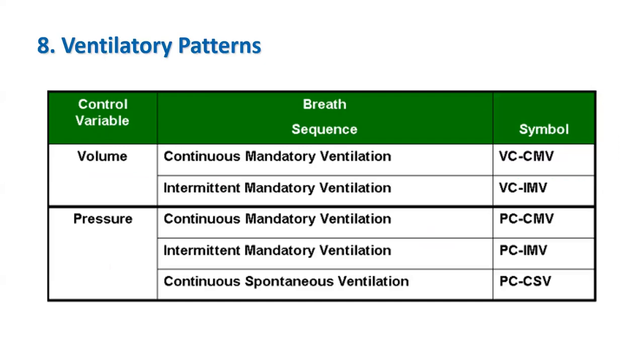Maxim 8 is simple but fundamental. It says that if you combine the control variable with the breath sequence, you get five basic ventilatory patterns found on all ventilators. These are volume control, CMV, and IMV, plus pressure control, CMV, IMV, and CSV. Volume control, CSV, is not possible because volume control implies machine cycling, so there can never be a volume control spontaneous breath.